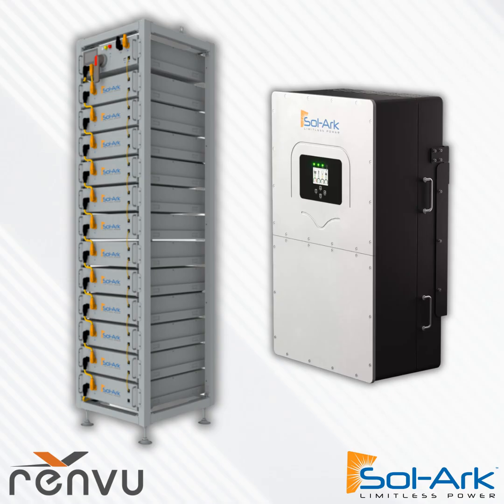Even with commercial agricultural applications, you get a lot of split phase electric service, and Sol-Ark is one of the only platforms that actually supports so many string inverters in parallel. Part of the reasoning is we have these oversized grid relay contactors that buy you a lot of tolerance when doing high amperage seamless transfer on large services. So if you're talking about large power applications on 240 volt service, Sol-Ark is by far and away the platform for that.